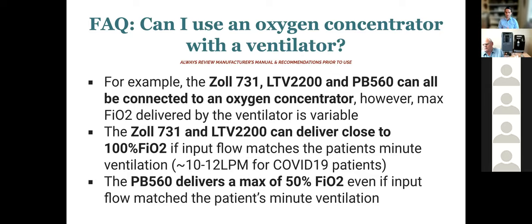And what that means is, if a patient is breathing really fast, they're going to need more oxygen. And if they're breathing faster than 10 liters per minute, and your oxygen concentrator maxes out at 10 liters per minute, you're going to have a problem. They're not going to be able to keep up. So you got to know what your vent can do, and you need to know what your patient needs and what the oxygen concentrator can deliver. On the PB560, it delivers a max of 50% FiO2 with up to 15 liters per minute going directly into the device.